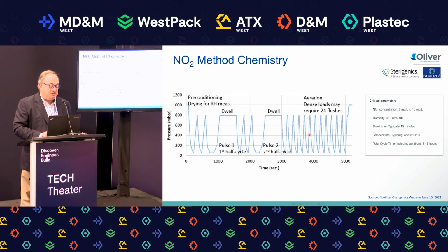This aeration process post-dwell is done to evacuate and make sure that the load is effectively both sterile as well as fresh air ready. Key takeaways: the dosing for an NO2 sterilization cycle typically ranges anywhere from 6 to, it says 15 mg per liter. That's on the high range. Typically we run around 10. Humidity ranges anywhere from 40% to 80% RH. Dwell time again is 10 minutes. Temperature, as I stated before, ranges from 18 degrees to 30 degrees C, on average 20 degrees C. And what's important to understand is that from the start of the load of the sterilizer to the end of aeration, you're looking at roughly a 4 to 8 hour process on average.